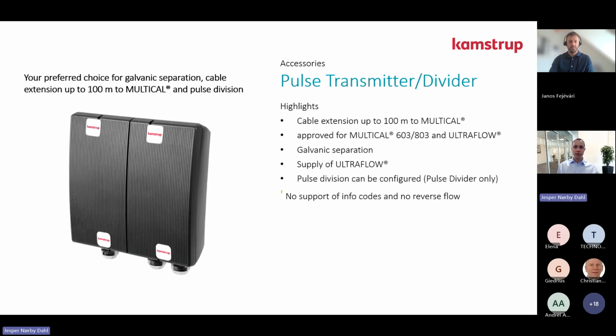Then we have the pulse transmitter divider. This is if you want to have longer cables than 30 meters. With a pulse transmitter, you can have up to 100 meters between flow sensor and calculator. Also, the divider is if you want to have it connected to, for example, a third-party calculator. But just one note to this, that if you use the pulse transmitter or divider, then you don't have the possibility of the serial communication, and you do not have the possibility of bidirectional, because it does not support info codes and it does not support this reverse flow.